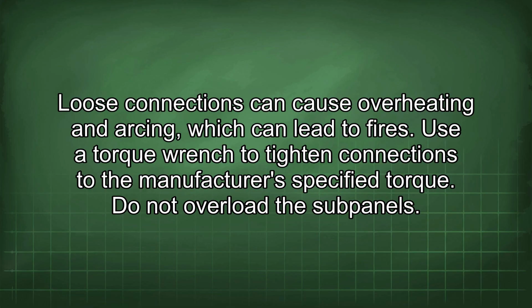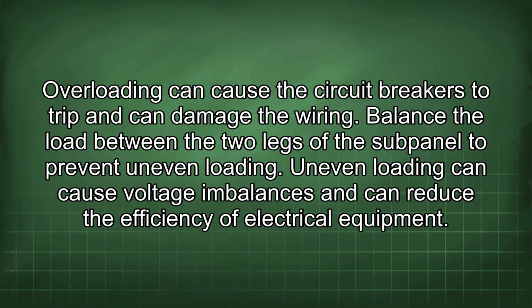Use a torque wrench to tighten connections to the manufacturer's specified torque. Do not overload the subpanels. Overloading can cause the circuit breakers to trip and can damage the wiring. Balance the load between the two legs of the subpanel to prevent uneven loading. Uneven loading can cause voltage imbalances and can reduce the efficiency of electrical equipment.